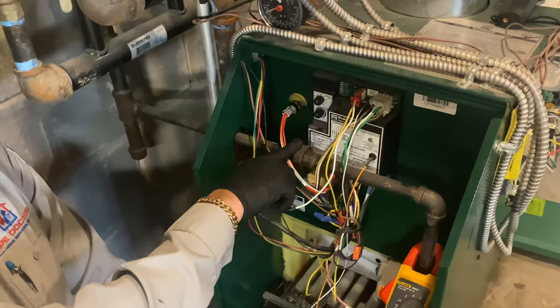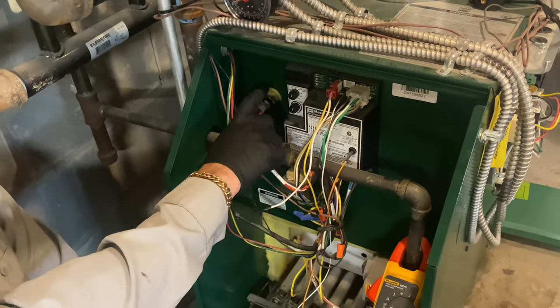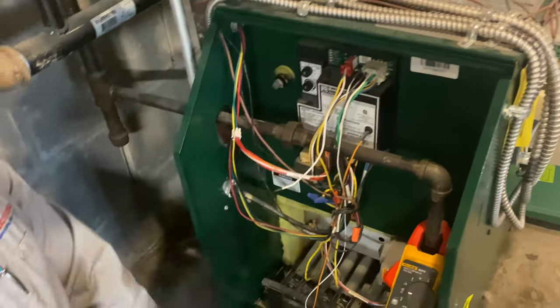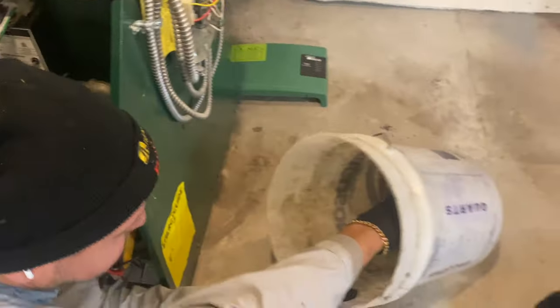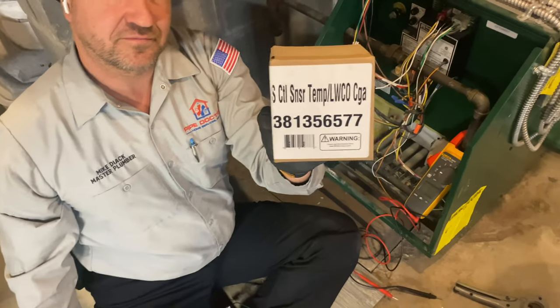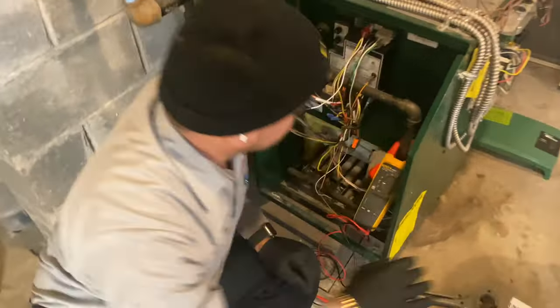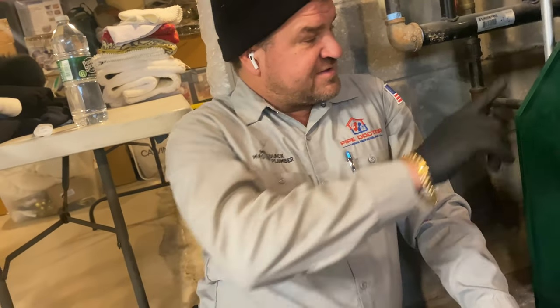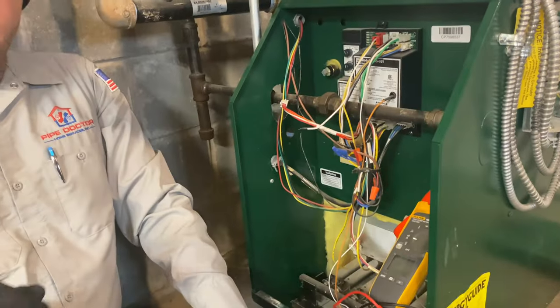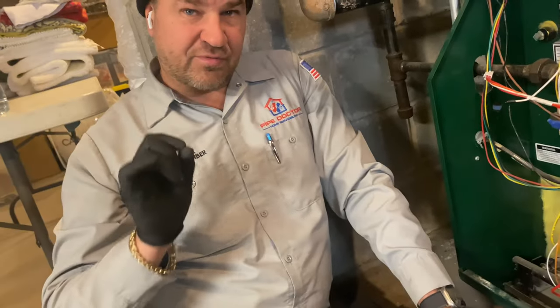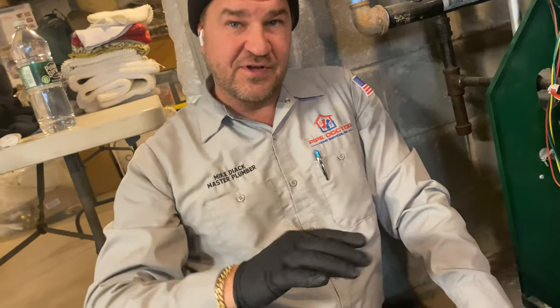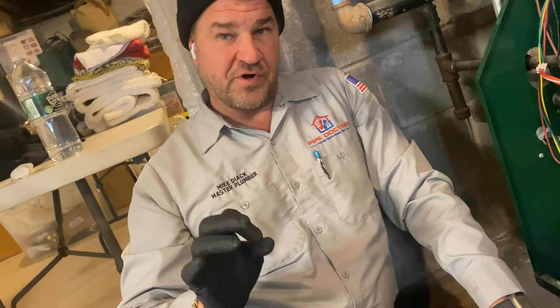The newer Weil-McLain, the CGA models, that temperature and pressure probe is also a low water cutoff. So if you're installing a Weil-McLain CGA series 3, the temperature probe is also the low water cutoff. It does not operate on pressure like some tankless combis do. It actually senses water where it shouldn't be.